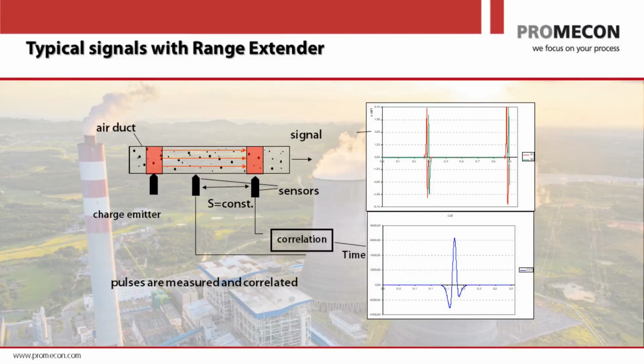So this helps you to measure when you have no dust. This is why we call this range extender. We had a certain amount of dust minimum level for our gas, like 800 micrograms. But with the range extender, that level goes to 0. We can measure absolutely clean air up to very, very dust congested air up to hundreds of grams per cubic meter. So we can measure nearly in all dusty and clean gases at the same time. Another reason why we call this range extender is that we found it also extends the minimum flow range that we can detect. So usually starting with 7-8 feet per second, that is now the lower limit that we can measure.